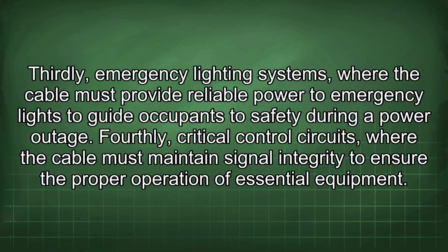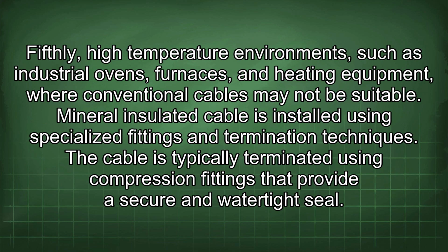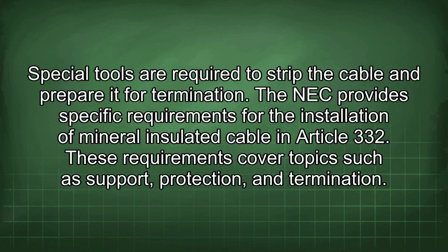Fourthly, critical control circuits, where the cable must maintain signal integrity to ensure the proper operation of essential equipment. Fifthly, high-temperature environments such as industrial ovens, furnaces, and heating equipment, where conventional cables may not be suitable. Mineral-insulated cable is installed using specialized fittings and termination techniques. The cable is typically terminated using compression fittings that provide a secure and watertight seal. Special tools are required to strip the cable and prepare it for termination.